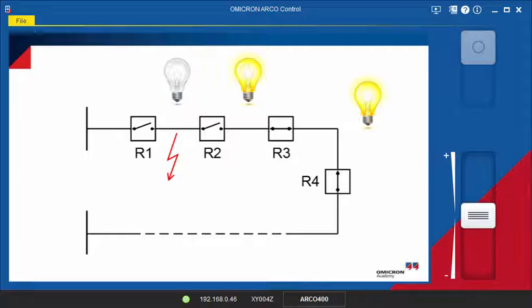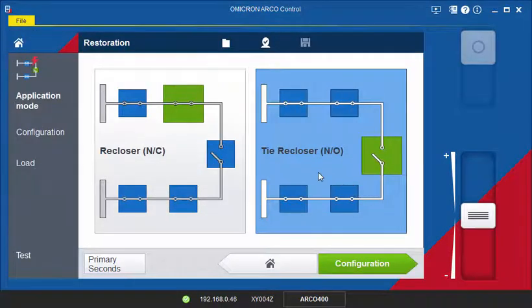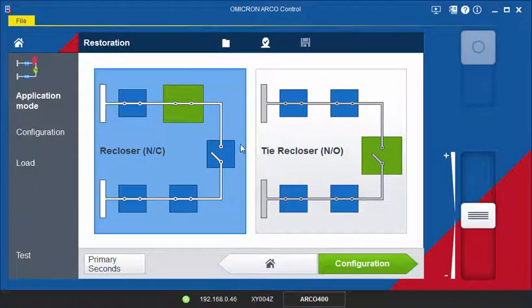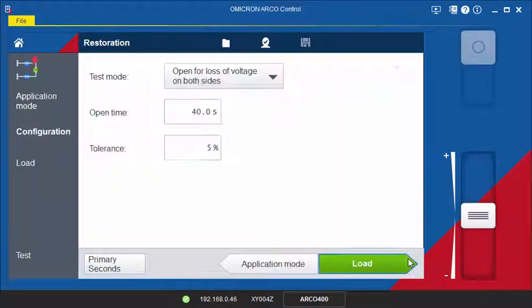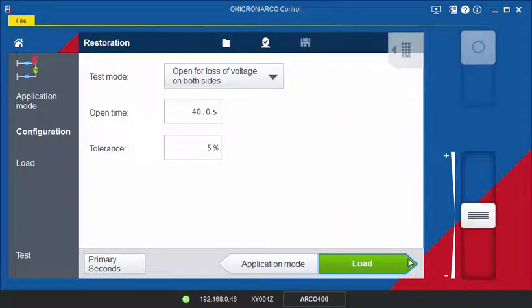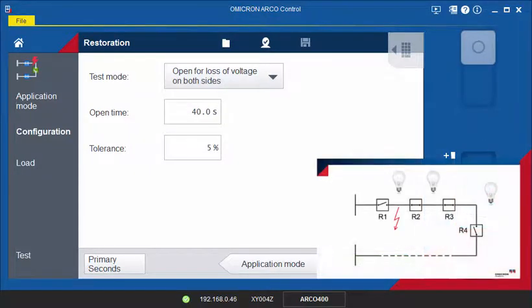Now, let's have a look at how the different functions are tested with the restoration tool. First, we want to test the correct behavior of the line recloser R2 after R1 has gone into a lockout state. R2 should open because of the loss of voltage.